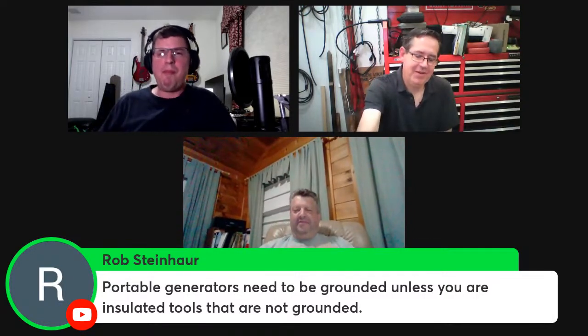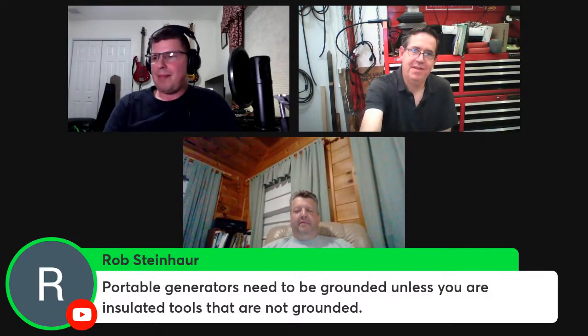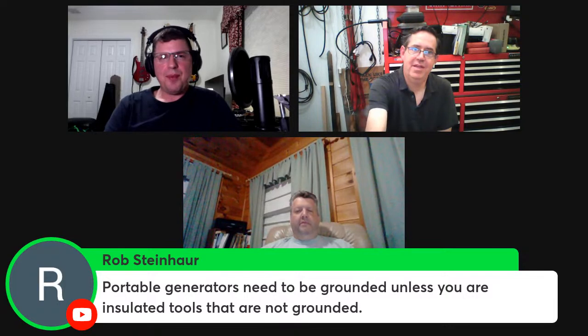If you have a bonded generator and a live wire hits the frame, it will trip the circuit breaker. If you have a floating generator, meaning a floating neutral, and a live wire hits the frame, the frame becomes live and no circuit breaker trips. So when you need a grounding rod, I don't know, but you definitely want it bonded if you're running it as a portable generator, so the breaker trips if something shorts out to the frame.